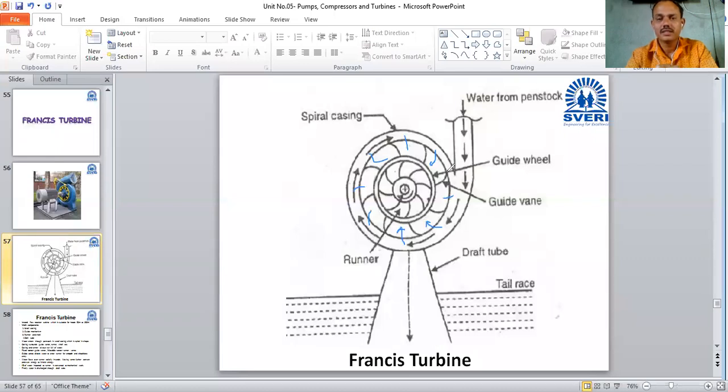Okay, the guide vanes are mainly used for this. The main purpose of the guide vanes is to regulate the flow all over the runner in the same amount. Now this middle one is the runner. This one is actually the moving part, or the actual turbine. If you observe here, you cannot get the shape of the turbine here. The turbine is like that.